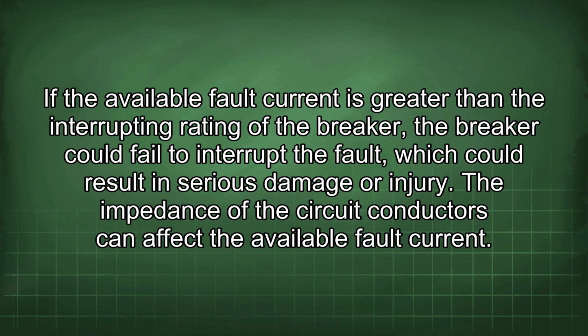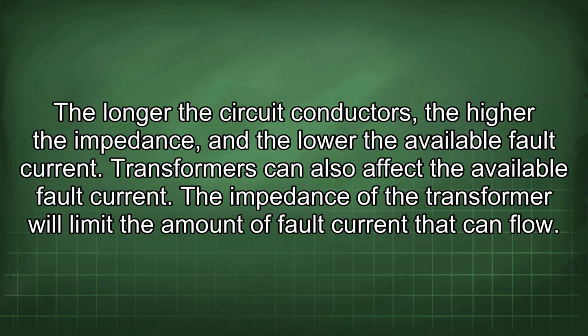If the available fault current is greater than the interrupting rating of the breaker, a breaker could fail to interrupt the fault, which could result in serious damage or injury. The impedance of the circuit conductors can affect the available fault current. The longer the circuit conductors, the higher the impedance, and the lower the available fault current.